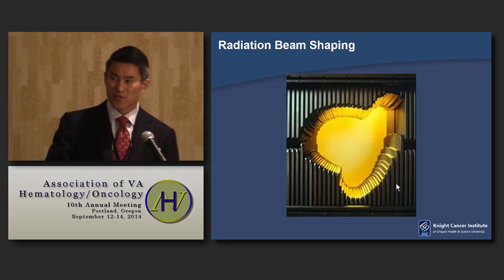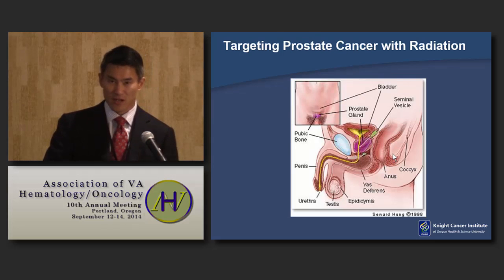These days, our shaping of the beam is accomplished with what we call a multi-leaf collimator. And this picture gives you the idea of the depth of how thick these leaves have to be. But these leaves are actually 2.5 millimeters thick, and they can slide in and out and shape the radiation. And I've got a little video that kind of demonstrates how that works.